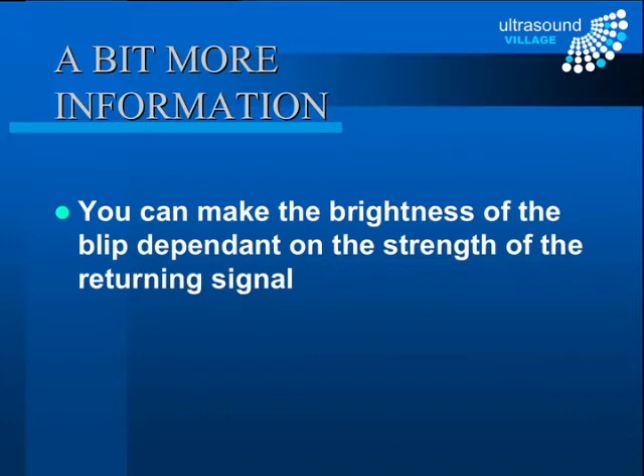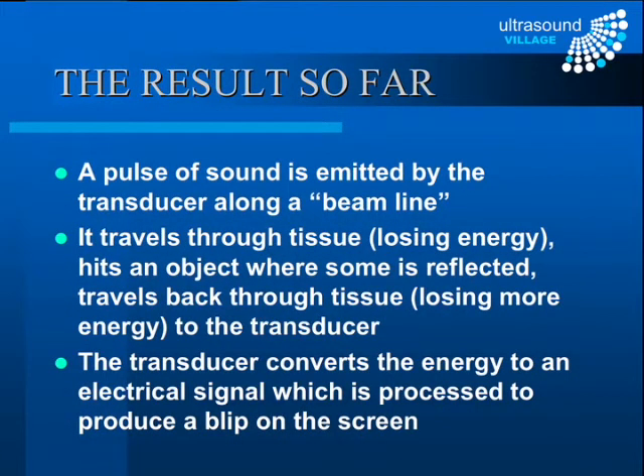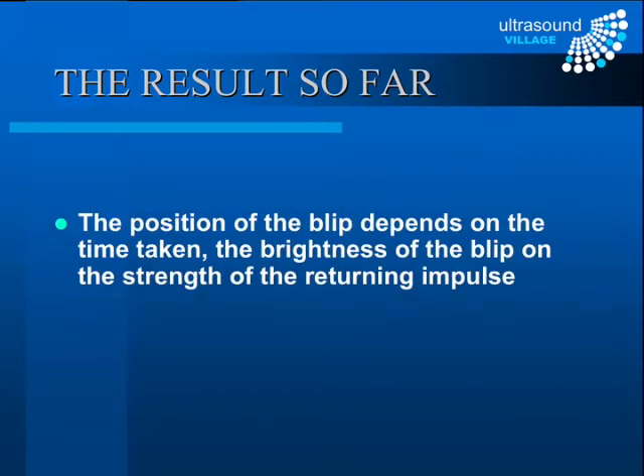When the machine receives the returning blip it works out the strength of that signal and adjusts the brightness of the blip on the screen accordingly. Putting it all together: the transducer emits a pulse along a beam line; the pulse travels through tissue losing energy, hits an object where some energy is reflected and most continues on; the reflected energy travels back undergoing attenuation again; the transducer converts it into an electrical signal processed to produce a blip on the screen. The position of the blip depends on the time taken, and the brightness depends on the strength of the returning impulse.